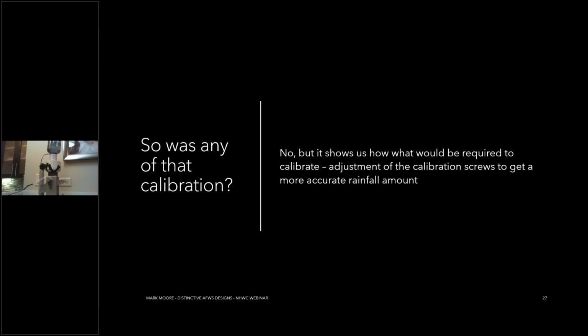Now, I'll also say that for the most part, depending on manufacturer specifications, if you're out in the field and you get an accuracy within 3%, I think that's pretty decent for a field calibration. If you're talking about something that you've got on your test bench like this, where there's no wind, there's no chance of drizzle, there's no big trucks driving past, it's worth it to work on that to get it to 1%.